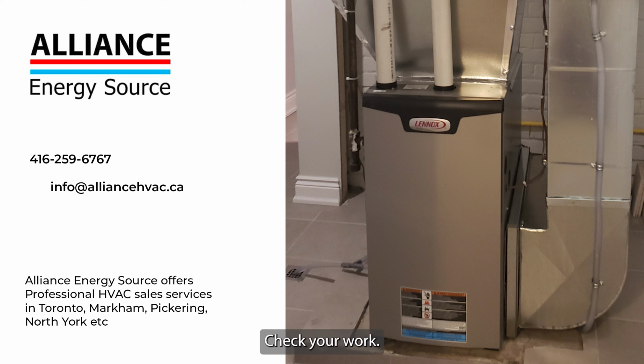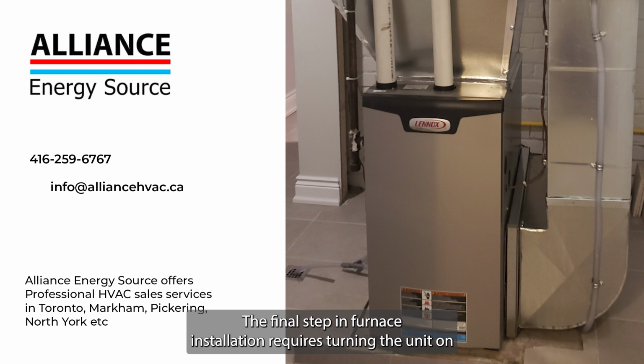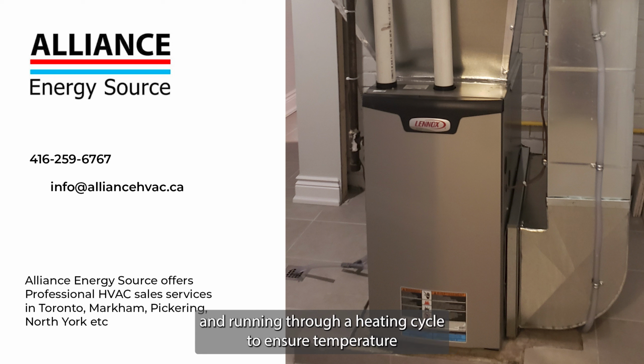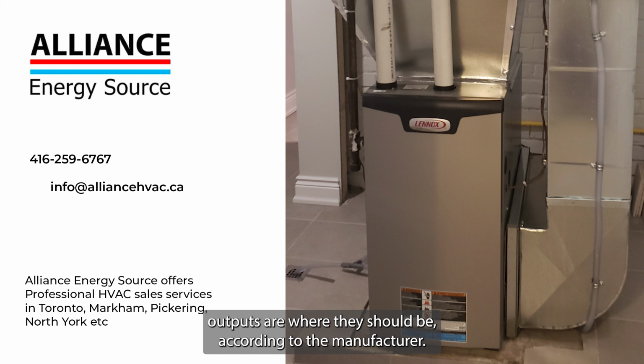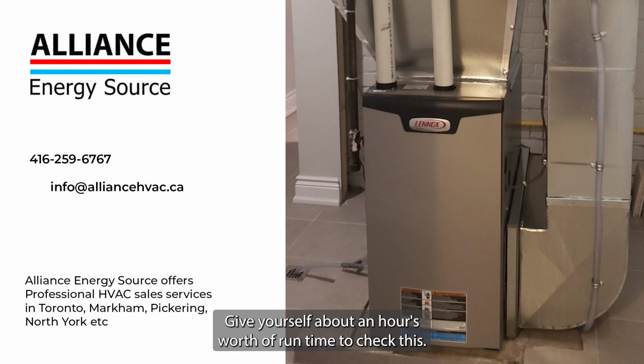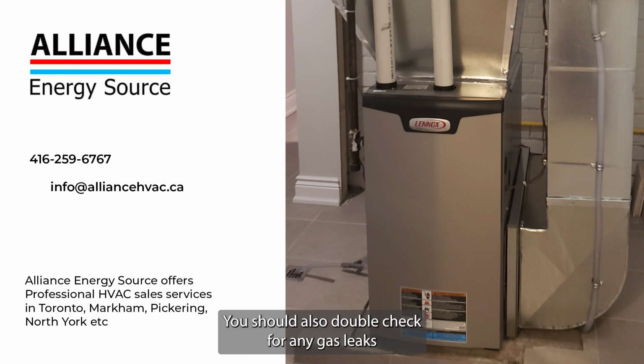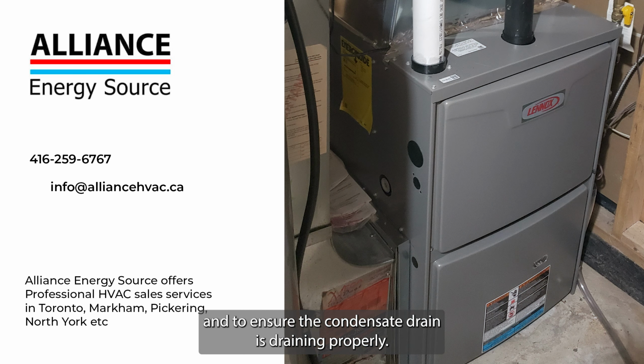7. Check your work. The final step in furnace installation requires turning the unit on and running through a heating cycle to ensure temperature outputs are where they should be according to the manufacturer. Give yourself about an hour's worth of runtime to check this. You should also double-check for any gas leaks, and to ensure the condensate drain is draining properly.